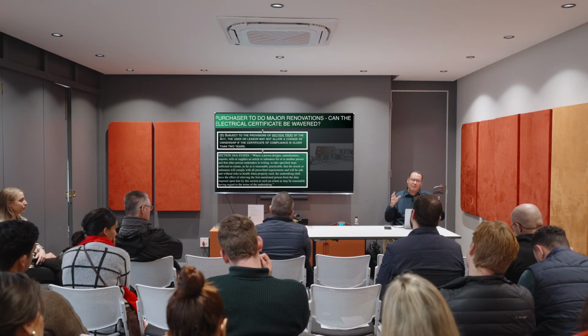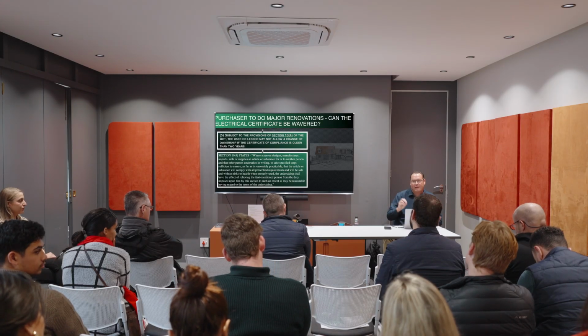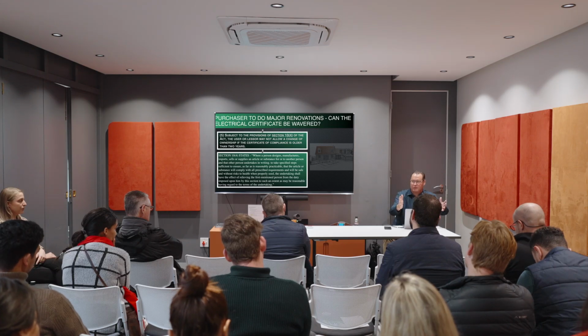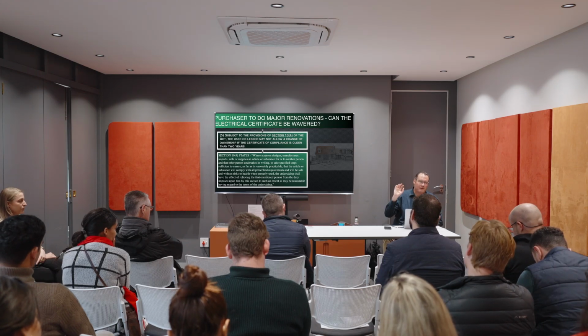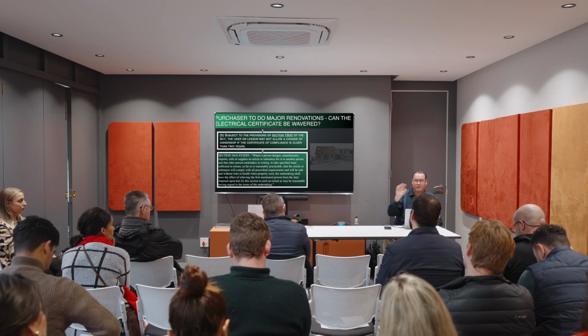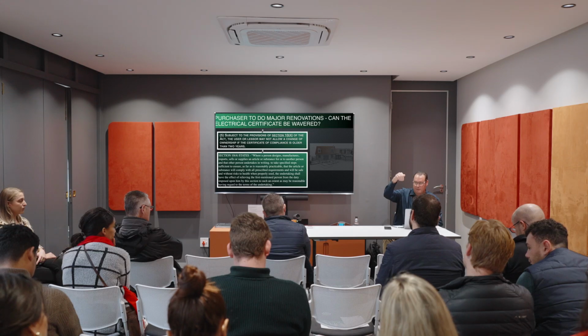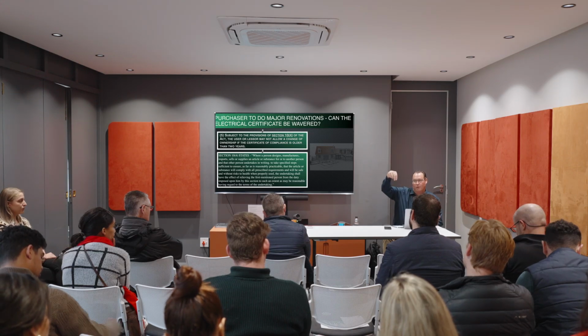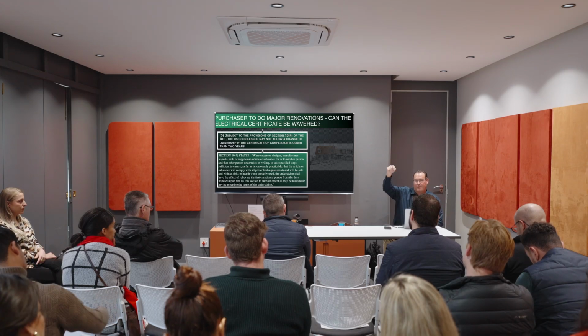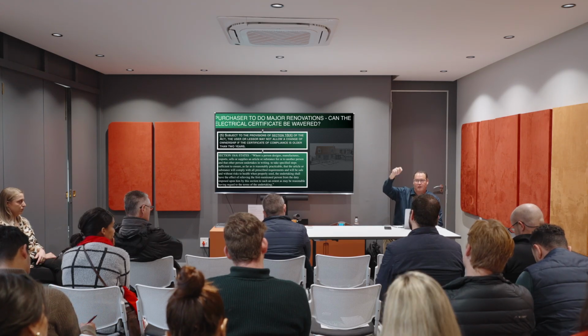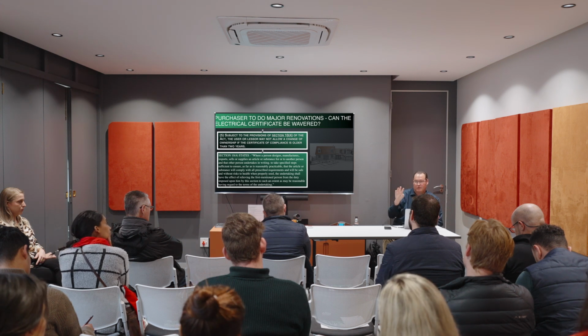Now let's get into the solar side. There are some companies that rent out solar systems. I'm not going to mention names because of the camera, but it's becoming such a headache because they install at rock bottom price, so they take shortcuts and squeeze everything into the main distribution board. We find single-phase houses with three-phase main switches because there's no space for two separate main switches. So they use a three-phase main switch: one pole for the main house supply, one pole for the solar, and the neutrals just run together through the neutral. They're trying to save space.